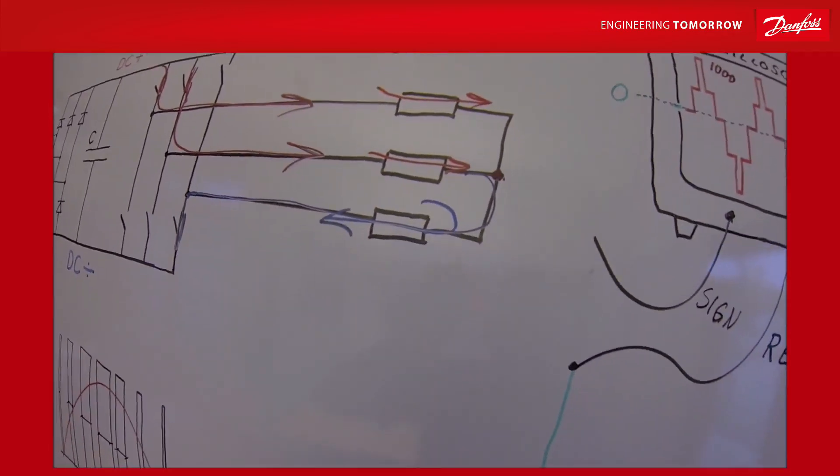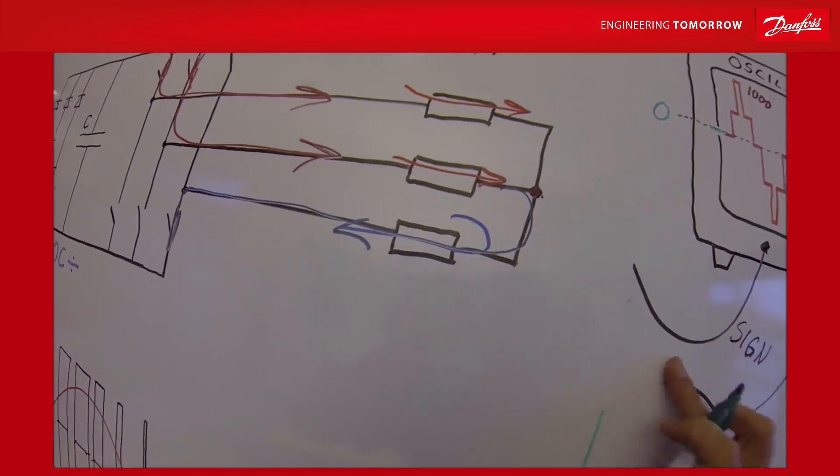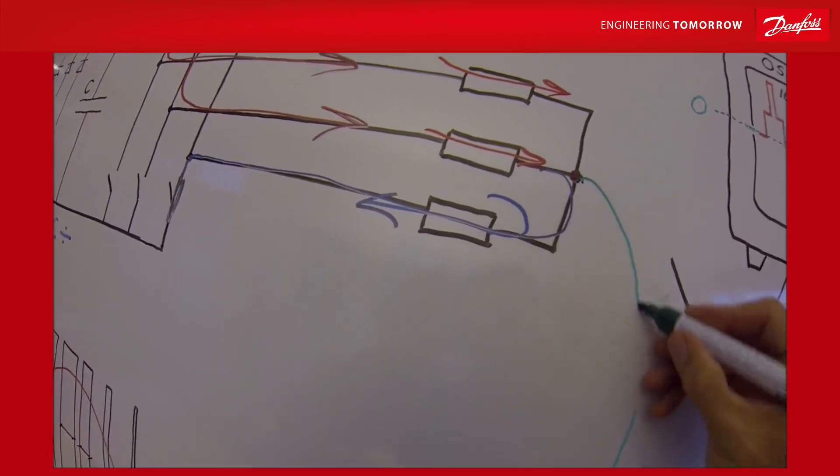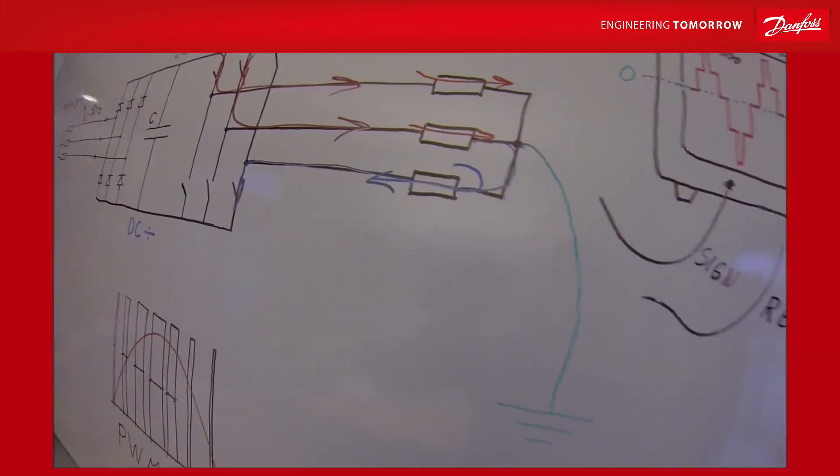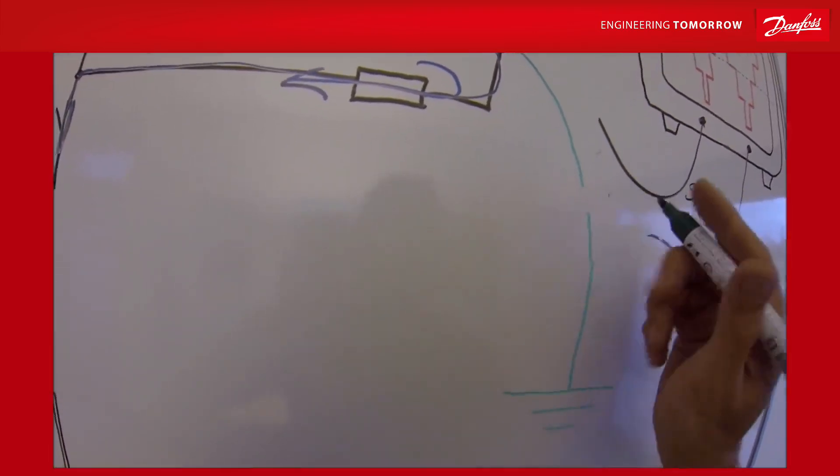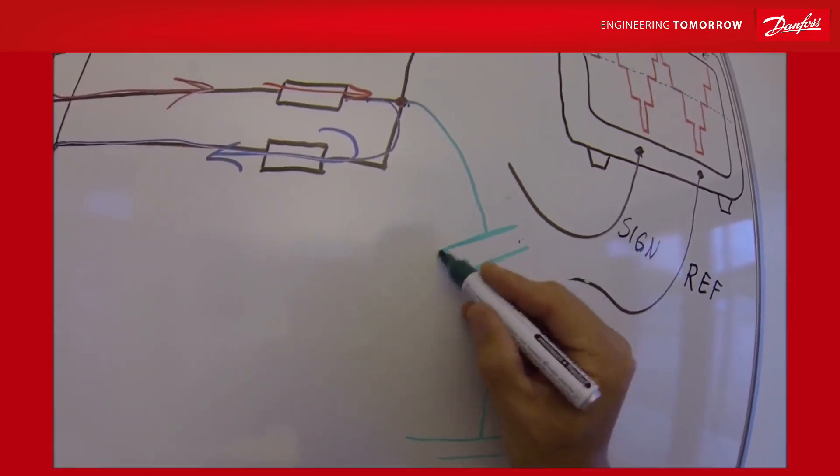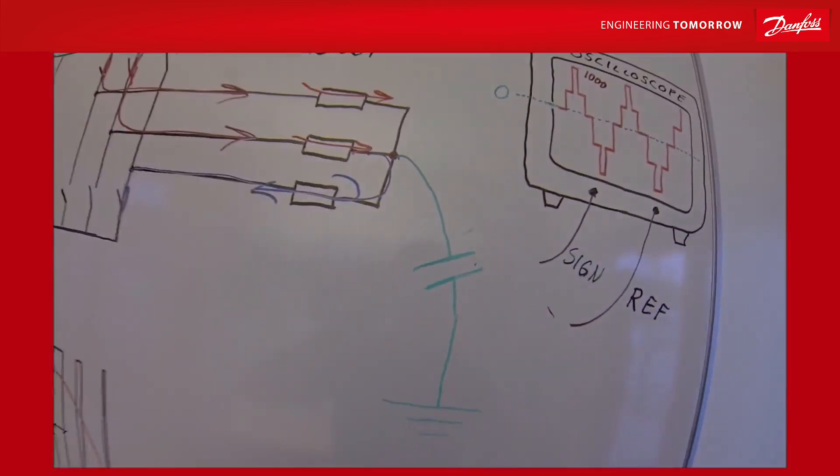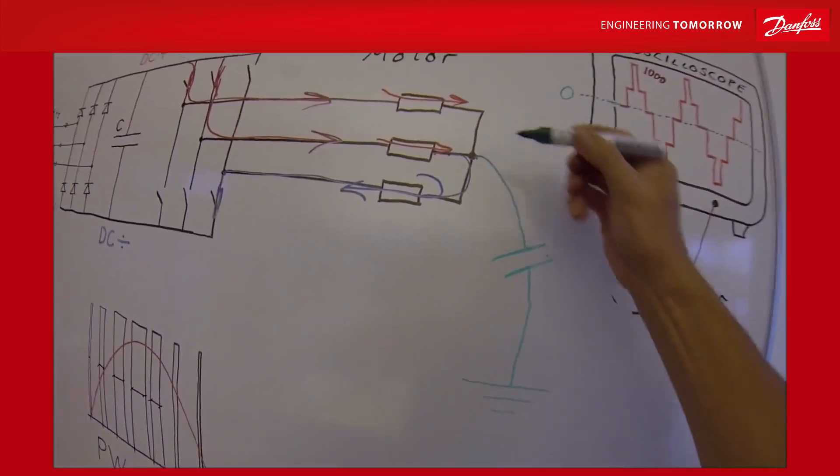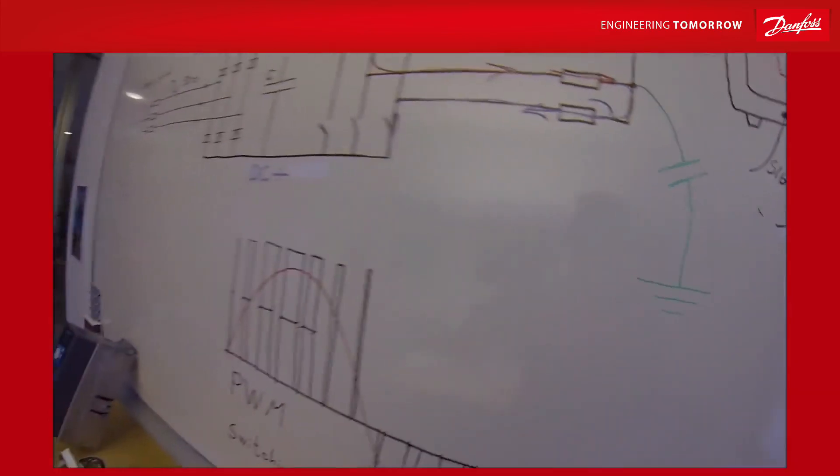What happens if we connect this star point to ground? Is that possible? Yes, especially with capacitive connection. There could be stray capacitance between the stator windings and the motor chassis.